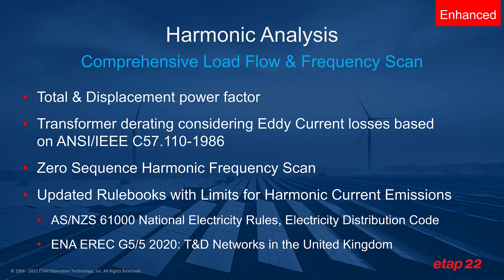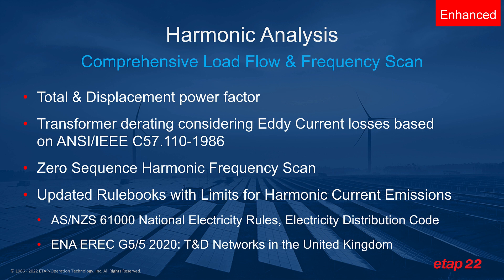Zero sequence harmonic frequency scan and updated rulebooks with limits for harmonic current emission that's used to alert or inform you that you are exceeding these limits at the point of interconnection. These new rules have been added based on Australian standard AS/NZS 61000 as well as ENA G5/5 2020, which is the emission limit for United Kingdom.